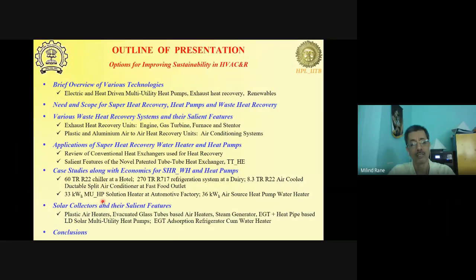So we'll see some of the features, because this is very important to improve the overall energy efficiency of the system. Now, just to give you a few examples, I have been using a multi-utility heat pump in my house, which is a 4-in-1 unit. It has been deployed since 2003, and it is still being operated. Even today, I took my bath with the hot water coming from that. It gives me air conditioning in 2 rooms, my dining area and the bedroom. It is a 1.5 ton compressor based system, and it gives me around 7 kilowatts of hot water.